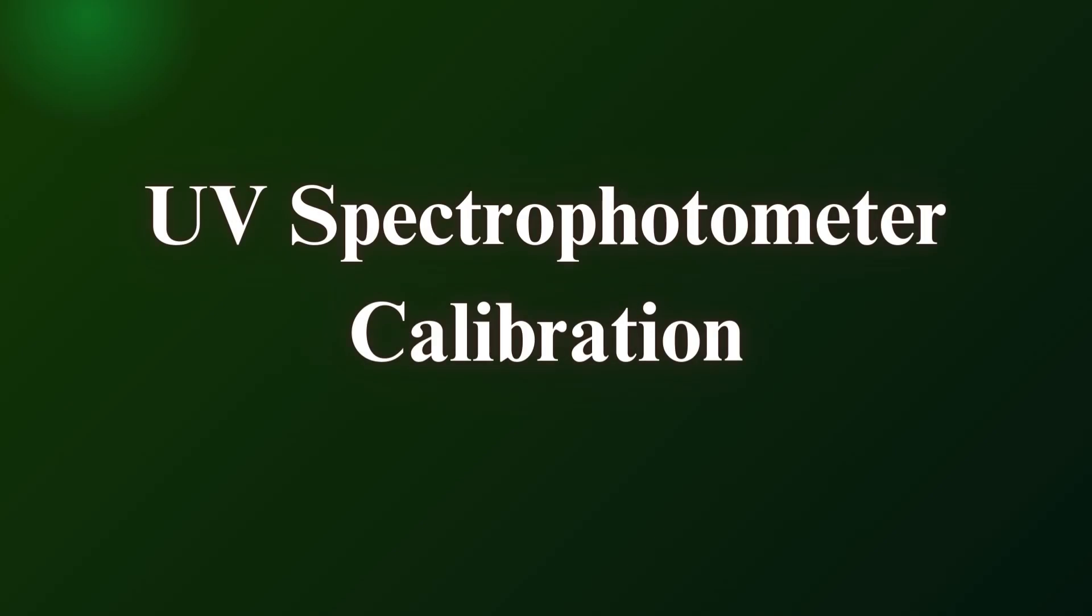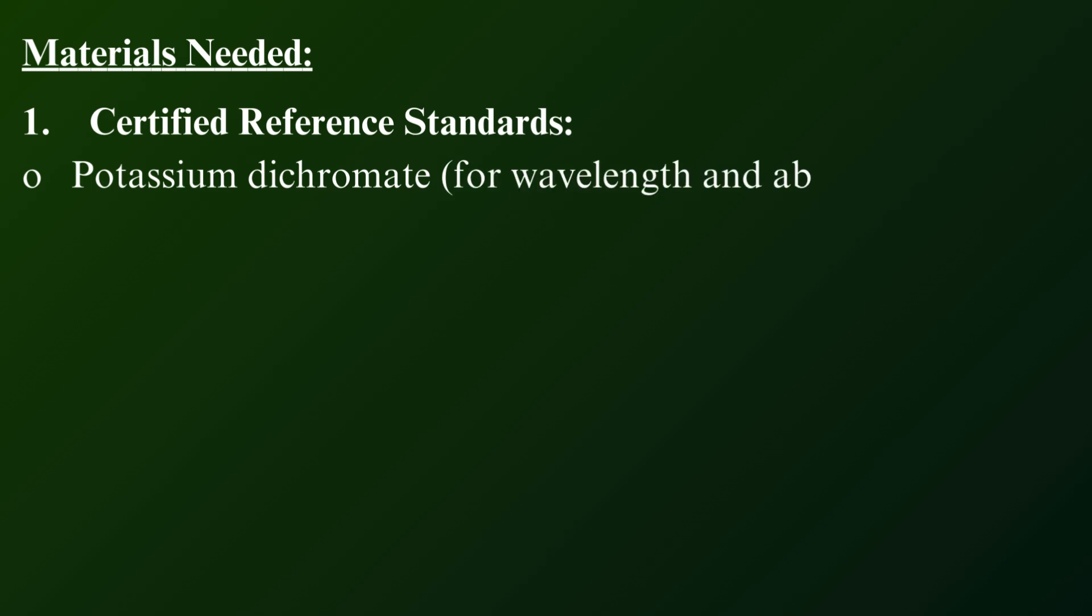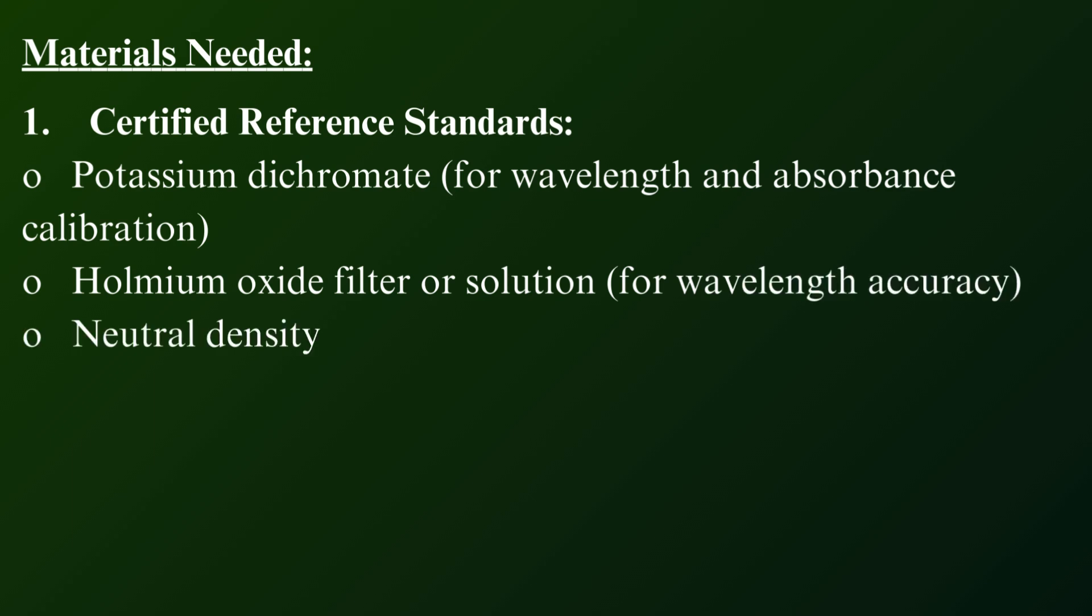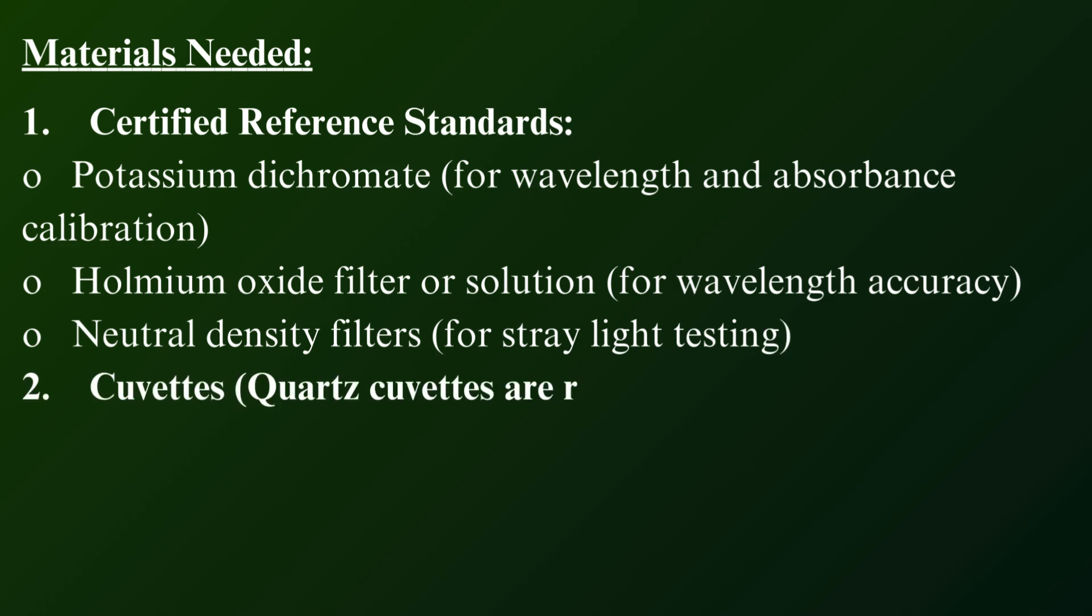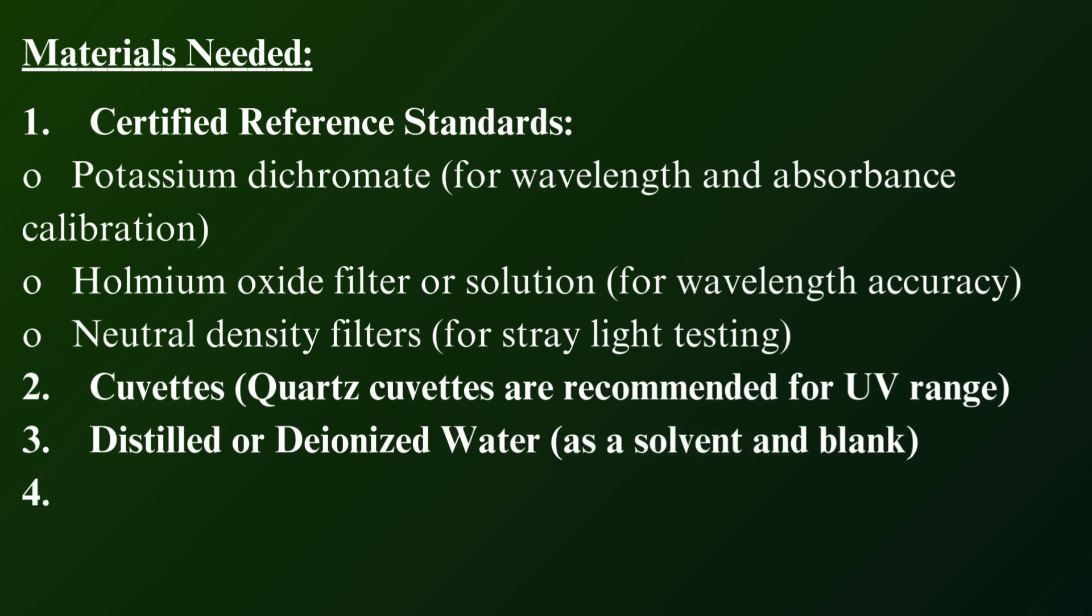UV spectrophotometer calibration. Materials needed: certified reference standards—potassium dichromate for wavelength and absorbance calibration, holmium oxide filter or solution for wavelength accuracy, neutral density filters for stray light testing, cuvettes (quartz cuvettes are recommended for UV range), distilled or deionized water as a solvent and blank.